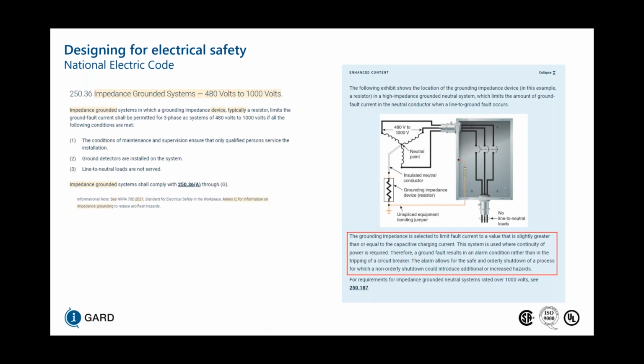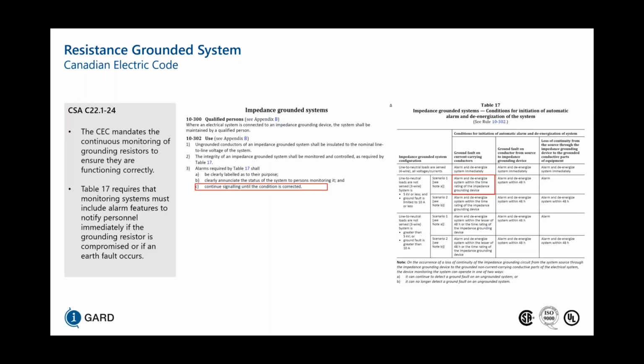Now, the alarm allows for the safe and orderly shutdown of a process for which a non-orderly shutdown could introduce additional or increased hazards. So refer to 250.36 if you're from the US side for impedance grounded systems and how you can abide by those requirements. Now in Canada, we have requirements for monitoring the resistor for both open and short circuit conditions. And in this case, we have to make sure that even when there's 0 volts and 0 amps, we are going to be monitoring the integrity of that resistor between its connection from XO to ground.